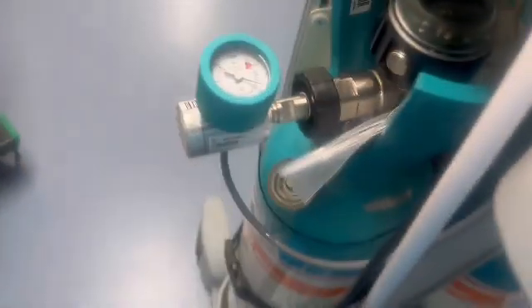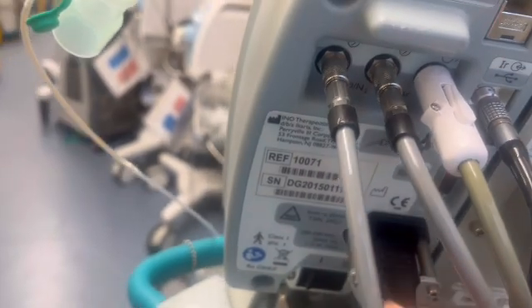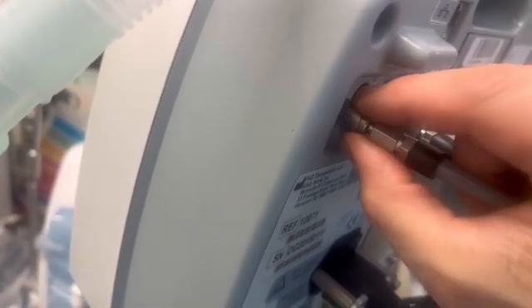Identify the pressure gauges on top of the cylinder. You need to make sure any gas primed in the cylinder head is removed. If the dial's not pointing to the red icon, there's gas in the cylinder head that you have to remove. To do this, turn the dial on the cylinder head clockwise to ensure it's completely closed. Identify the grey lead that transports the nitric from the cylinder to the machine. Find the very end of the lead and, very much like a blood pressure cuff, push it towards the back of the machine until it's released.